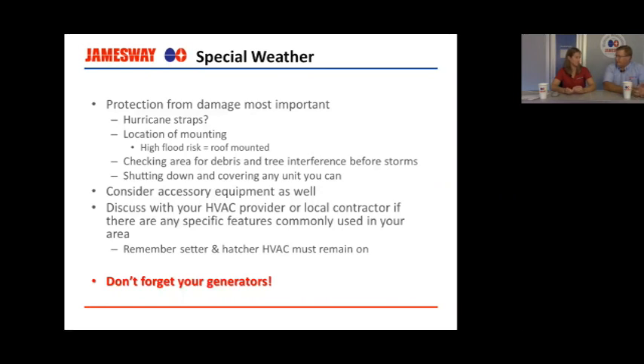So if somebody has an existing hatchery, then that opportunity still exists? Yeah, for sure. And definitely if you have an existing hatchery, we know that the average life of machines is longer than the average life of HVAC units. So at some point you're going to need to be replacing that HVAC, maybe before you replace your incubators and hatchers. It's always a good idea to have that checked with us rather than putting in what you put in back in the 70s or the 80s. Don't just put in the same size unit because, like we talked about, climate is probably changing. And so that's a concern there.